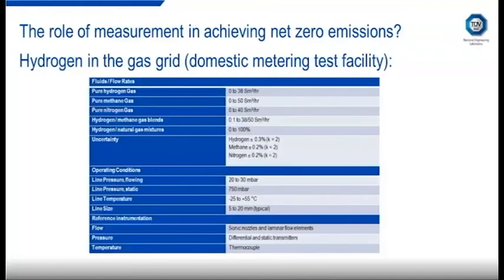In terms of the operating ranges, we have a maximum flow rate of 50 standard cubic meters per hour. We can operate with pure fluids or mixtures of hydrogen, methane, and nitrogen. The expected measurement uncertainties are 0.2% for methane and nitrogen for the mass flow rate and 0.3% for hydrogen. The test conditions at the test section will be low pressure because domestic gas meters are typically used at 20 millibar. So it's not really a high pressure facility, although the temperature range should be quite wide.